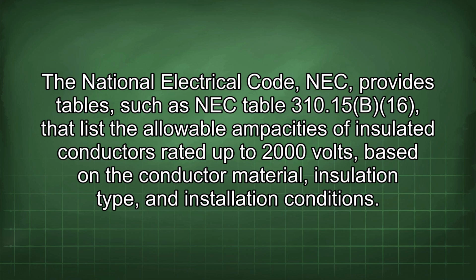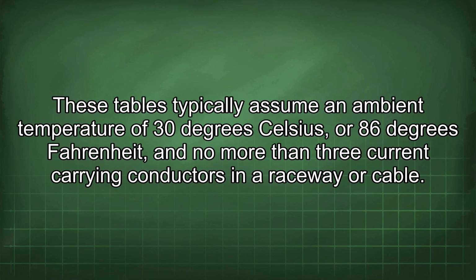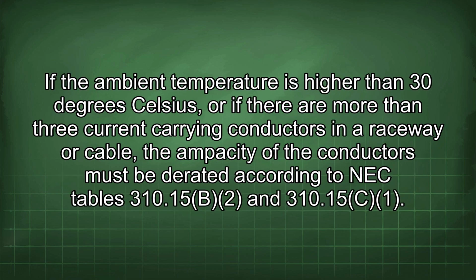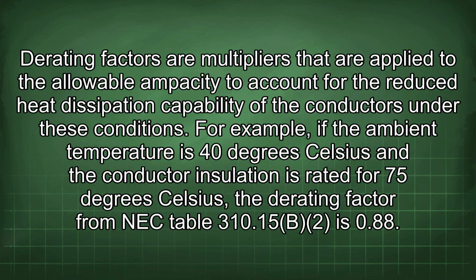These tables typically assume an ambient temperature of 30 degrees Celsius or 86 degrees Fahrenheit and no more than 3 current-carrying conductors in a raceway or cable. If the ambient temperature is higher than 30 degrees Celsius, or if there are more than 3 current-carrying conductors in a raceway or cable, the ampacity of the conductors must be derated according to NEC Tables 310.15(B)(2) and 310.15(C)(1). Derating factors are multipliers that are applied to the allowable ampacity to account for the reduced heat dissipation capability of the conductors under these conditions.